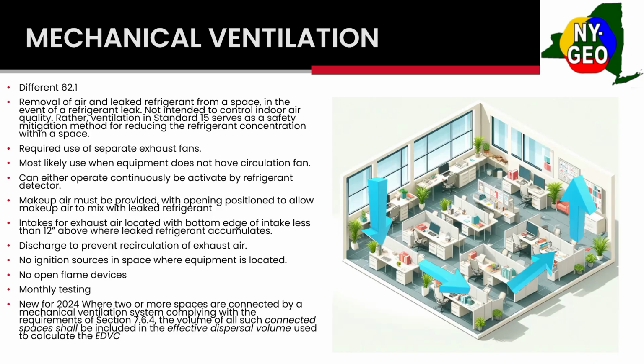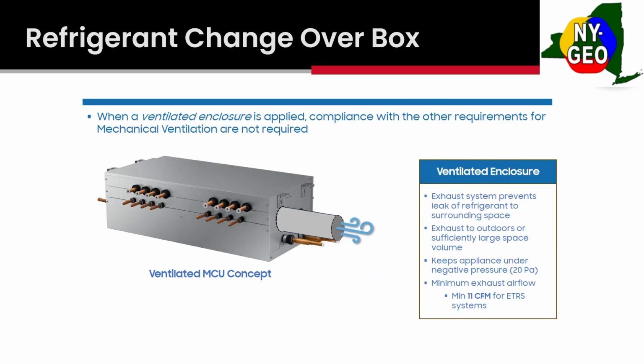All right, so this is new for VRF systems. This is your refrigerant changeover box. So this is a high concentration of refrigerant in this box. You can no longer just throw this up into a corridor or a machine room. It's going to have a duct collar on it now to exhaust that refrigerant out. And this needs to stay in a negative pressure because this can contain several pounds of refrigerant. You don't want that leaking out.